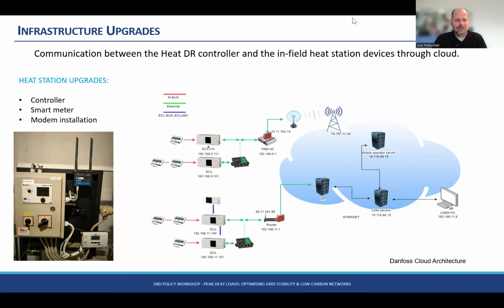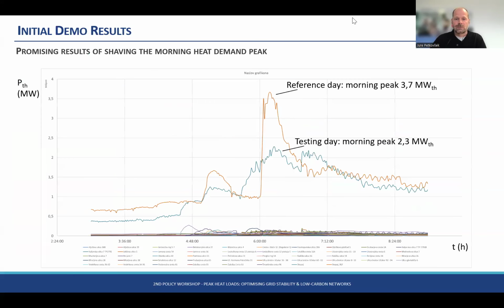We can see 3 devices which were added to the heat station. One is a new controller within the electrical cabinet. On the right below there is a smart heat meter, and above there is a communicator able to communicate with the central heat demand response controller through radio or GSM connection. This connection is established via respective providers' clouds. We are using 4 clouds, and here the Danfoss cloud is presented, which enables communication between the Danfoss controller and the central heat demand response controller.